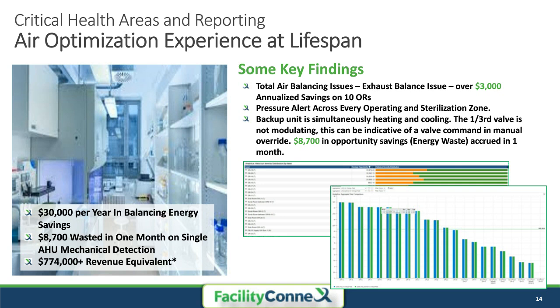Having a system like this running in real-time gives you the assurance you need to watch these conditions. But check this out—every specialized air handling area you monitor tends to have backup units, and typically you turn those on from time to time. When they turned the backup units on, we were watching it on the monitoring-based commissioning system and saw the unit cause a simultaneous heating and cooling condition. It ran a few times over the month and added up to $8,700 in a single month.